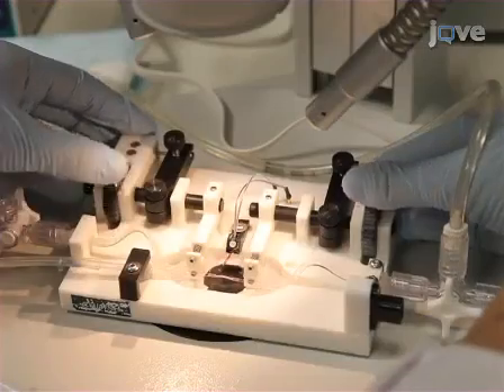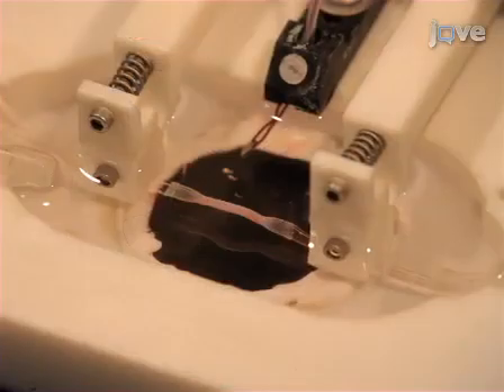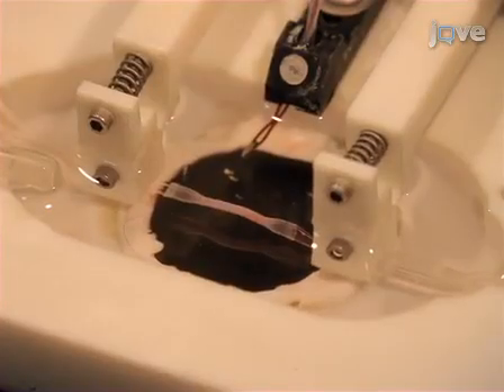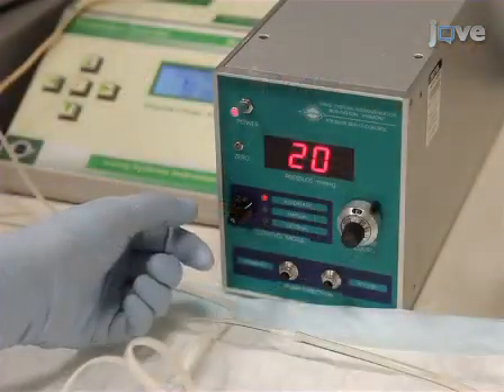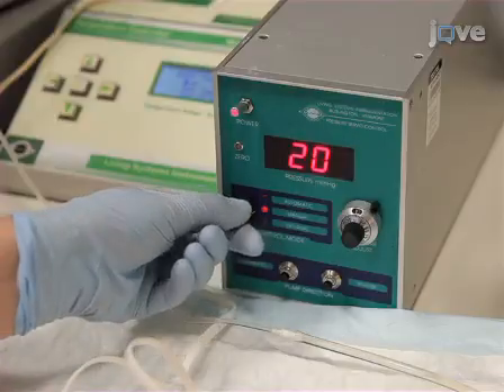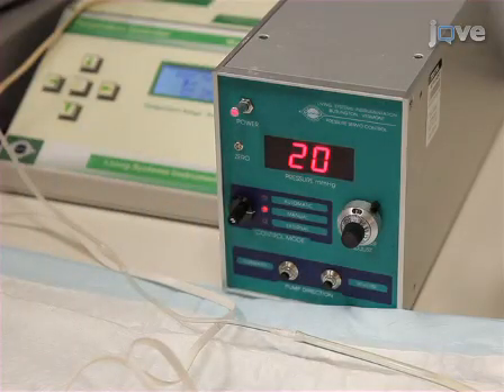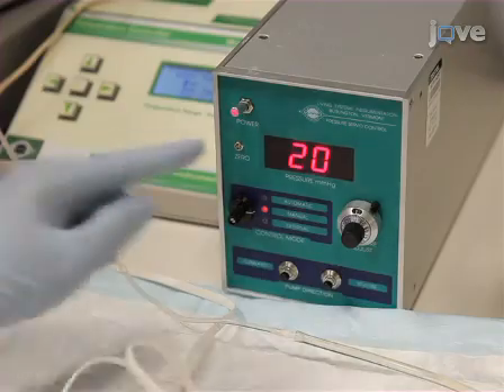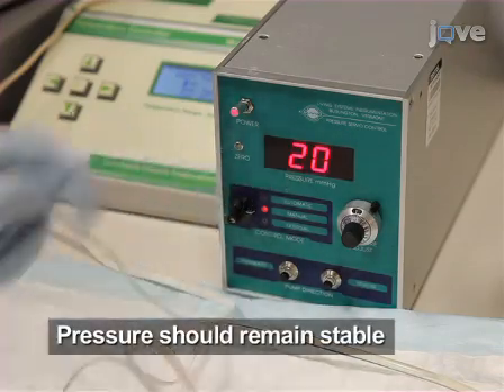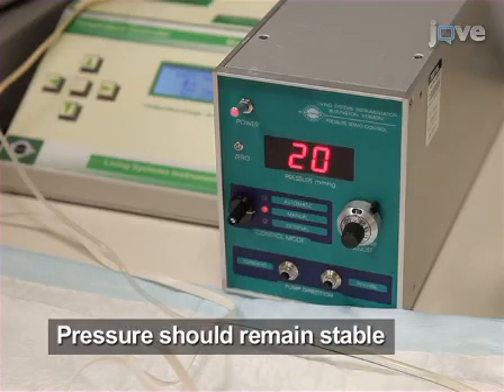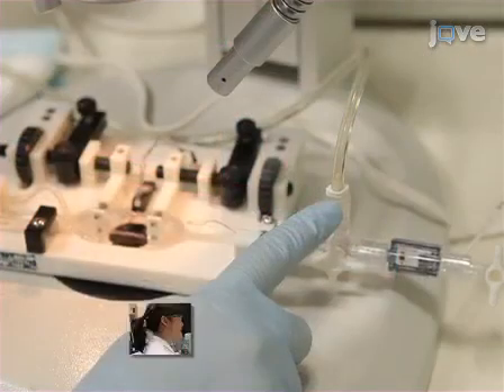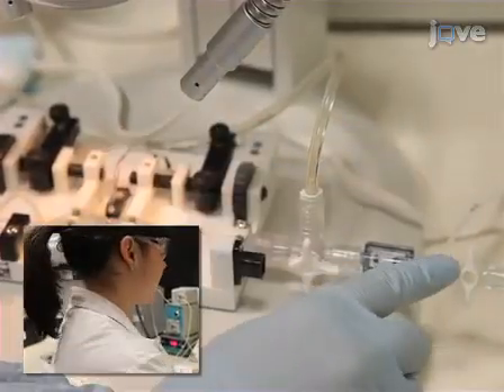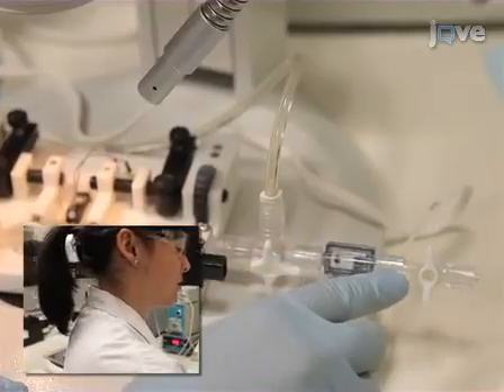To begin pressurizing the vessel, adjust the cannula holders to ensure no bend or stretch in the vessel. With P1 and P2 closed to the chamber, switch the pressure servo from automatic to manual. Check on the pressure servo to verify that there's no drop in pressure within 10 seconds. A decrease in pressure indicates a leak is present and the connections and transducer need to be secured in place to ensure they are pressure tight.